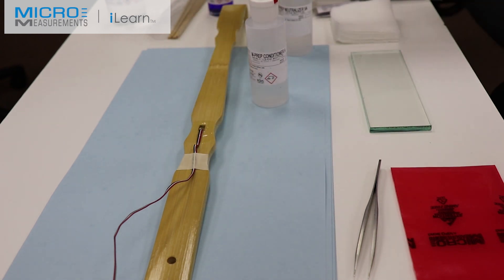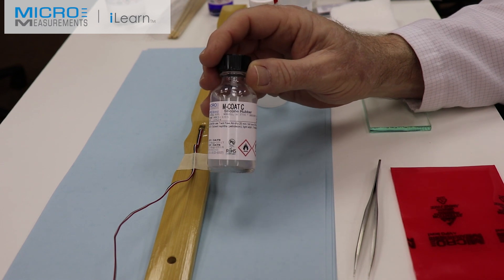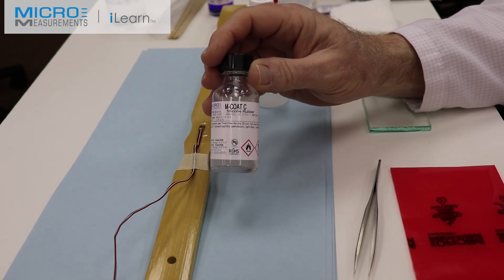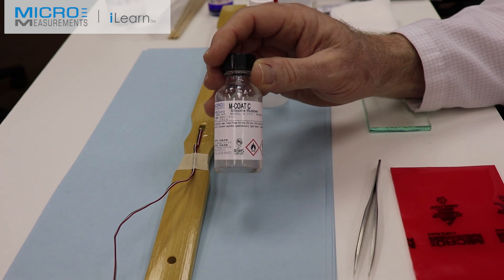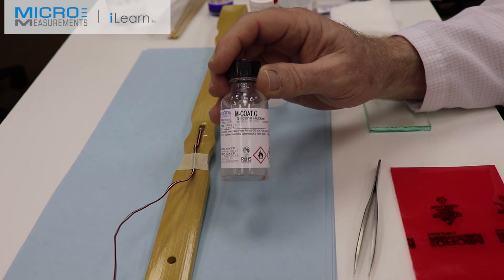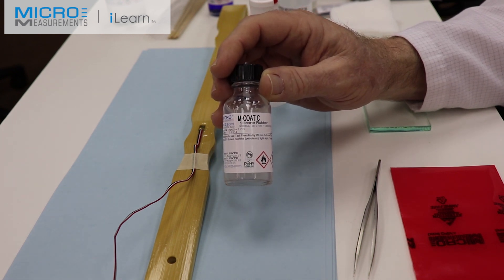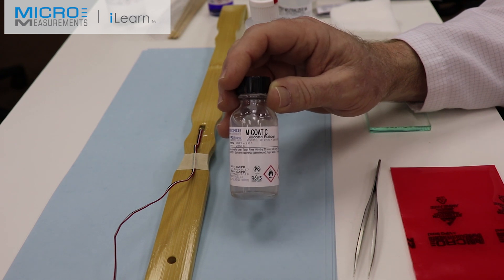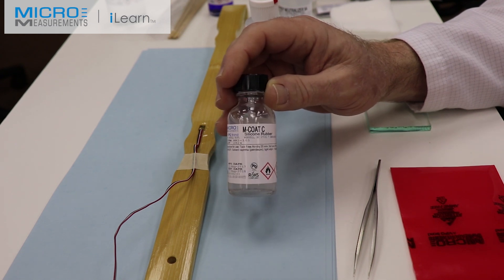And finally, as an environmental protection because of the possible elongations and the lack of reinforcement that we want on this particular application, we're using our M-Coat-C. It's a room temperature vulcanizing rubber which is benign and doesn't affect the strain gauge electrically or mechanically.